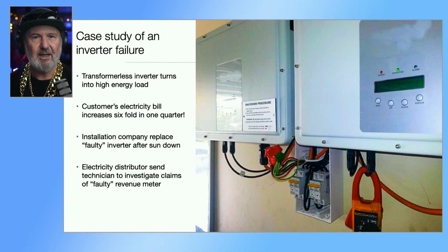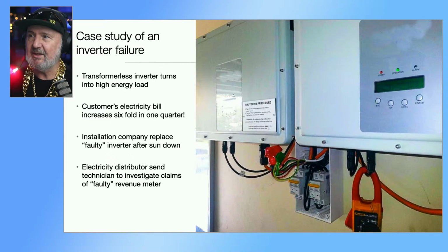So the installation company, and I imagine it was probably wintertime, often faults are done at the end of the day when you've done all your real work. You rush around and do quick swap outs of faulty inverters. So they swapped out an inverter without testing it because it was dark. Same problem came back the next day. The customer thought maybe it's the electricity meter, maybe the meter's faulty and it's recording export as import and something's wrong with the metering. So they contacted their electricity distributor and the distributor sent out a technician who analysed the system.